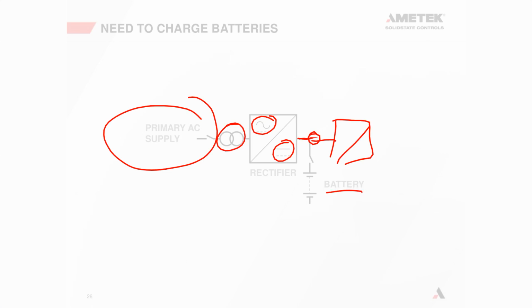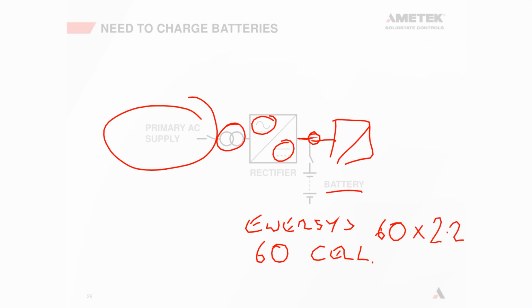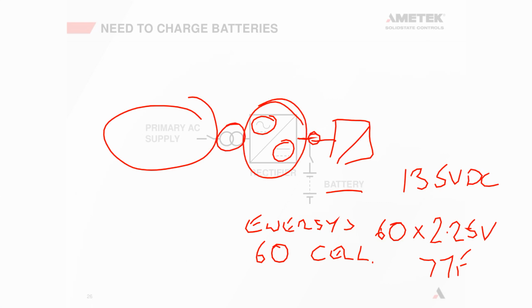It is the battery. So let's say Enersys, which is one of the major industrial battery manufacturers, say, okay, if you have a 60 cell lead acid battery, then you're going to have to float charge your system at 60 cells times 2.25 volts, which is what they usually stipulate at 77 degrees Fahrenheit, which equals 135 volts DC. So the output of our rectifier charger is specifically chosen only to charge the battery. That is the most important thing we're trying to do. Keep the battery charged optimally, okay?